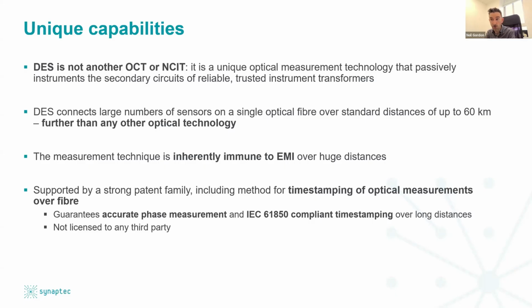To our knowledge, no other method exists other than using our patent to achieve that performance. What that means is that any other optical sensing technology will incur a significant and increasing timestamp error the further away sensors are installed on the fiber, meaning that accuracy standards and protocol compliance cannot be guaranteed. Now, this is Synaptec's patent, and we do not license that to any third party, so it's unique to the DES platform.